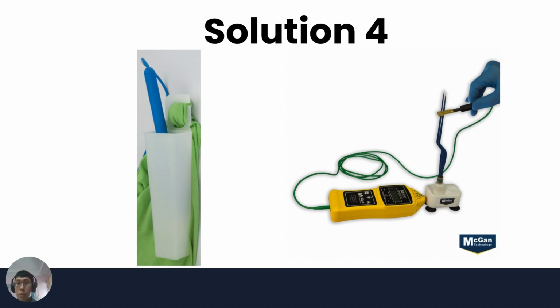Solutions to direct application safety issues. The first recommendation: when not using the active electrodes, they should be kept in well-insulated safety holsters. It's essential to use electrodes which have a layer of insulation to minimize the risk of direct coupling, and they should be regularly checked on the sterile surfaces between uses.